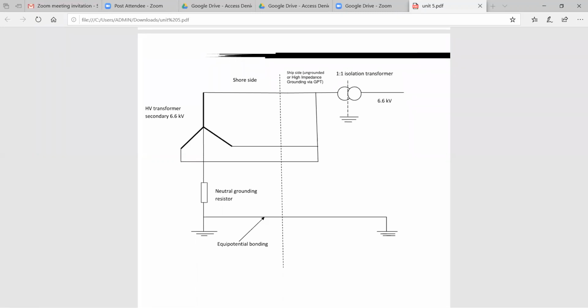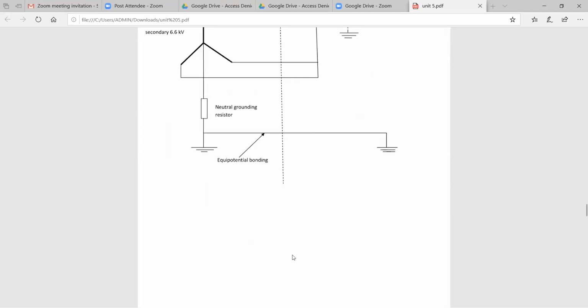But if you consider a short circuit fault, what will happen? In a short circuit fault, keep it in your mind, the voltage value starts to decrease and the current value starts to increase. So the primary side impedance and secondary side impedance are not balanced with each other. If the impedance is not balanced, the impedance relay starts to react. When the impedance relay is energized or reacts, the respective contacts change position. The transformer is isolated, that means primary and secondary will be automatically isolated. There is no voltage transformation between primary and secondary. So this is the operation considered in this type of circuit.